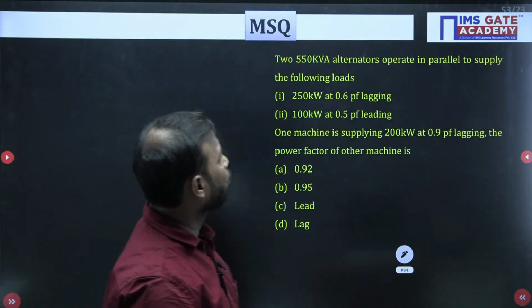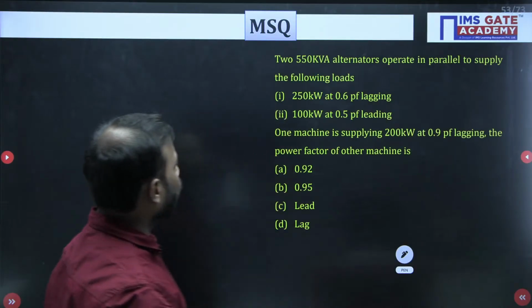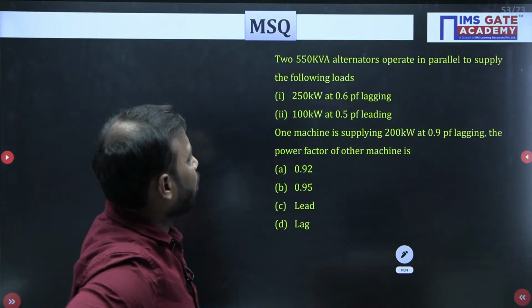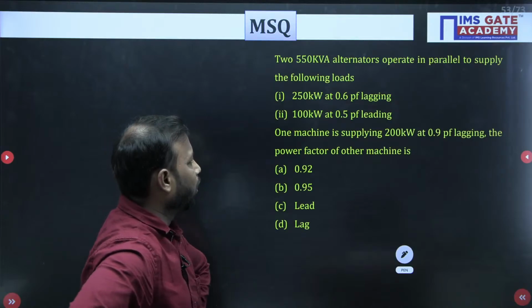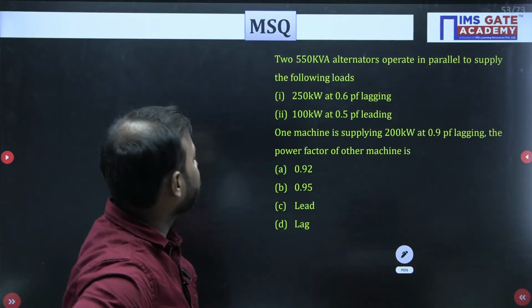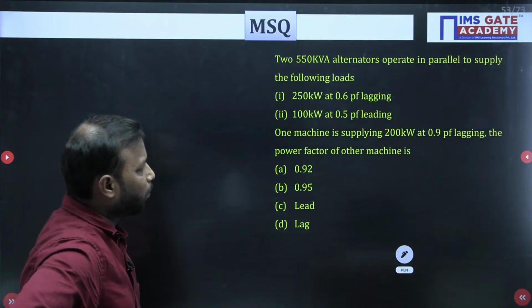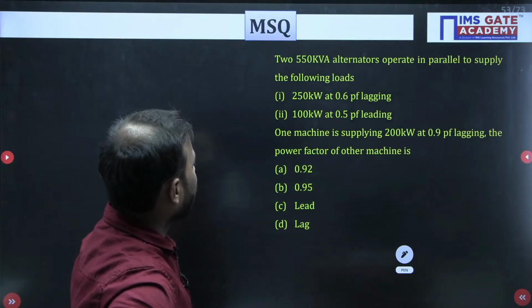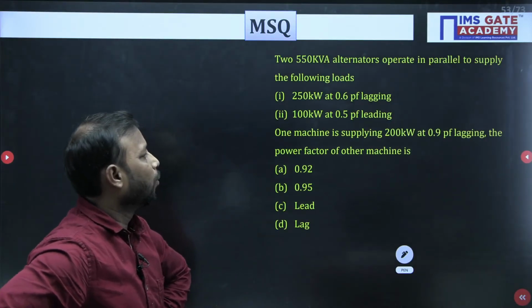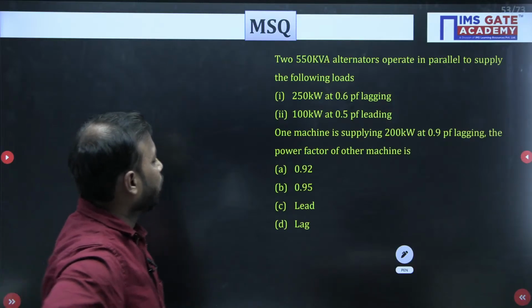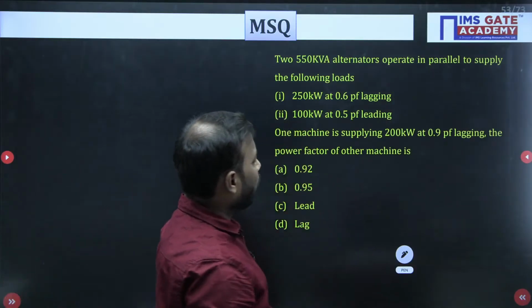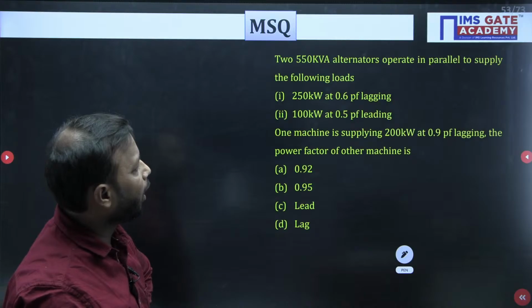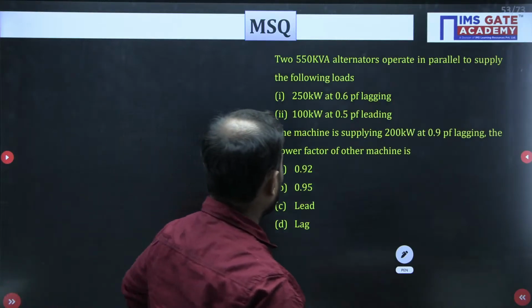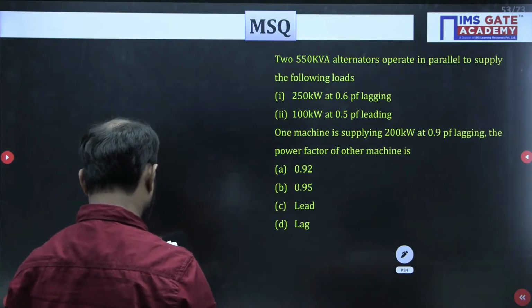Again, it is an MSQ type question. Two 550 kVA alternators operate in parallel to supply the following loads. First load is 250 kilowatt at 0.6 power factor lagging. Second load is 100 kilowatt at 0.5 power factor leading. One machine is supplying 200 kilowatt at 0.9 power factor lagging. The power factor of the other machine is to be found.